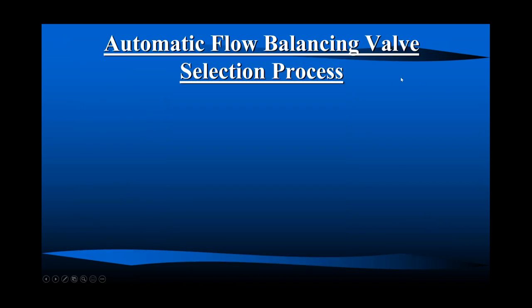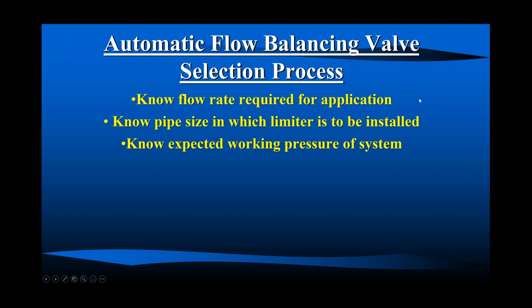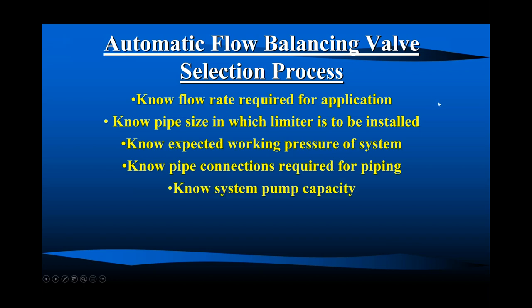If you think automatic flow balancing valves are the right product to make your system perform as designed or intended, right? What do you have to know? You have to know the flow rate required for the application. You already know that. You already sized your terminal units. You already have the GPM, design day flow. That's what you have to know. Pipe size, of course. Working pressure. What kind of pipe connections, threaded, sweat, and the like. Maybe PEX, right? System pump capacity, is it over 75 feet, less than 75 feet, so we can get the right pressure control range, where the flow limiters are in relation to where the pump is.